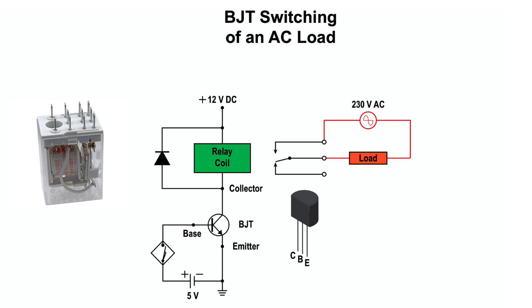The example shows the way a BJT is used to control an AC load. With the proximity switch open, no base or collector current flows, so the transistor is switched off. The relay coil will be de-energized, and voltage to the load will be switched off by the normally open contacts. When the transistor is in the off state, the collector current is almost zero, the voltage drop across the collector and emitter is 12 volts, and the voltage across the relay coil is zero volts.